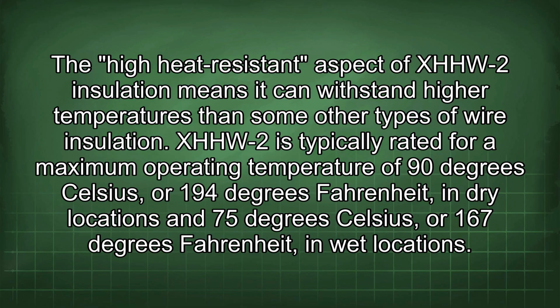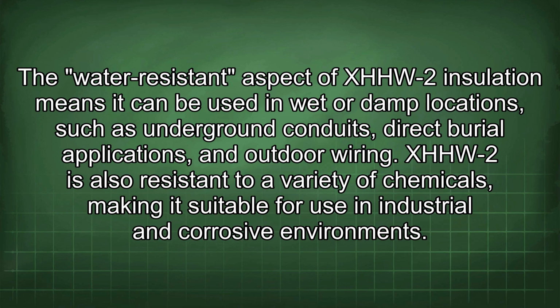XHHW-2 is typically rated for a maximum operating temperature of 90 degrees Celsius or 194 degrees Fahrenheit in dry locations and 75 degrees Celsius or 167 degrees Fahrenheit in wet locations. The water-resistant aspect of XHHW-2 insulation means it can be used in wet or damp locations such as underground conduits, direct burial applications, and outdoor wiring.